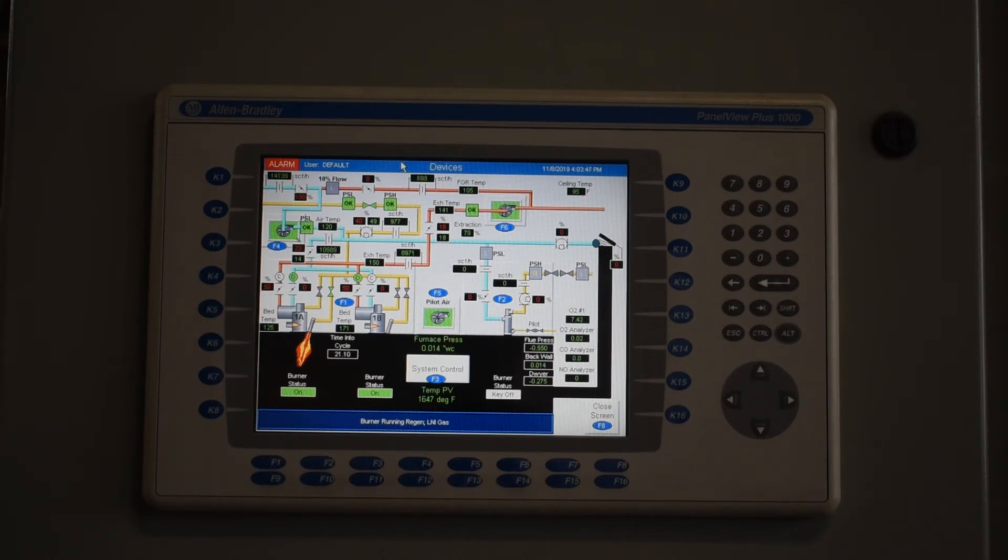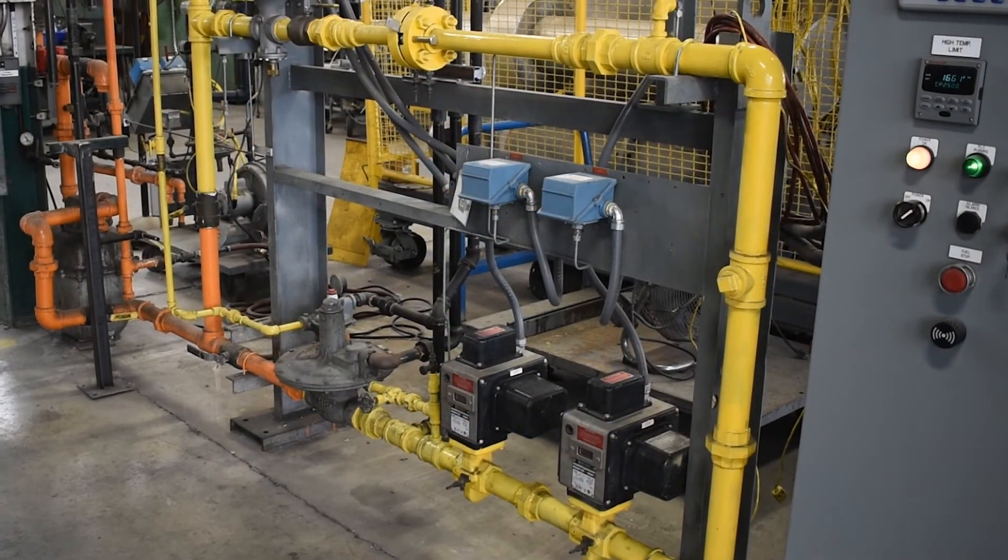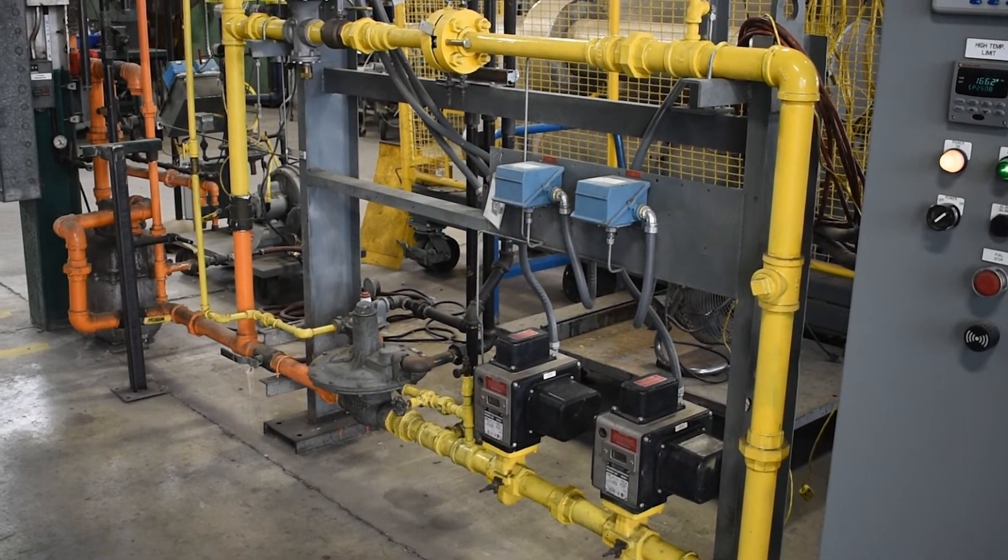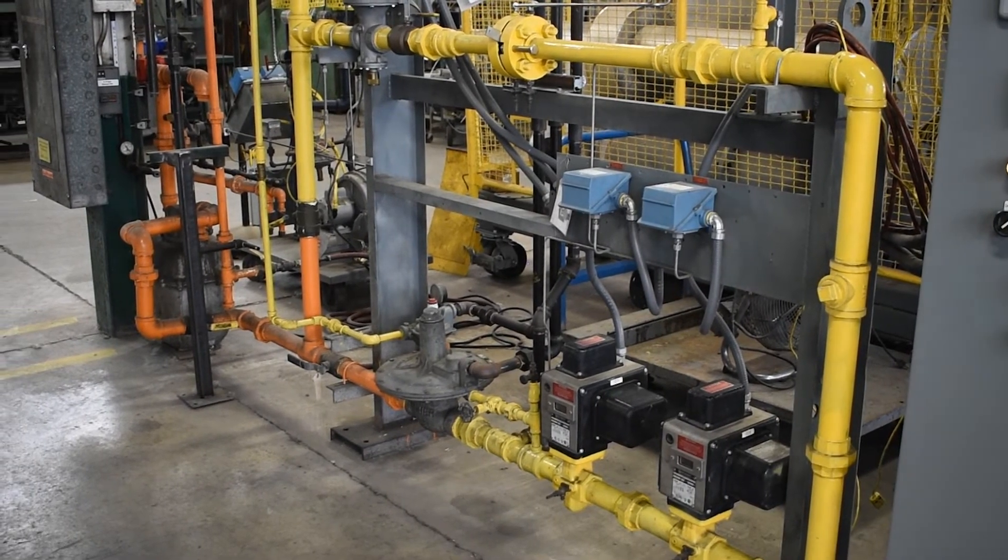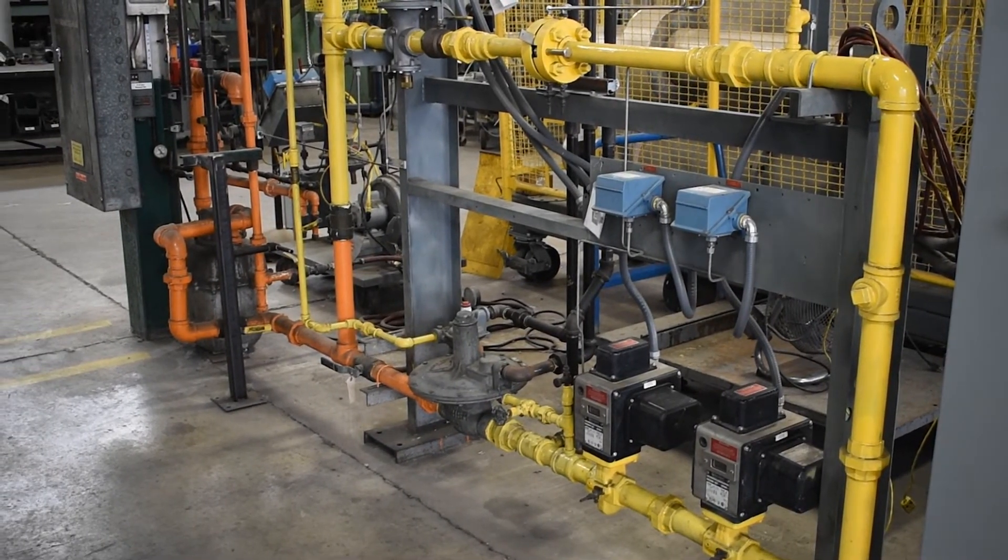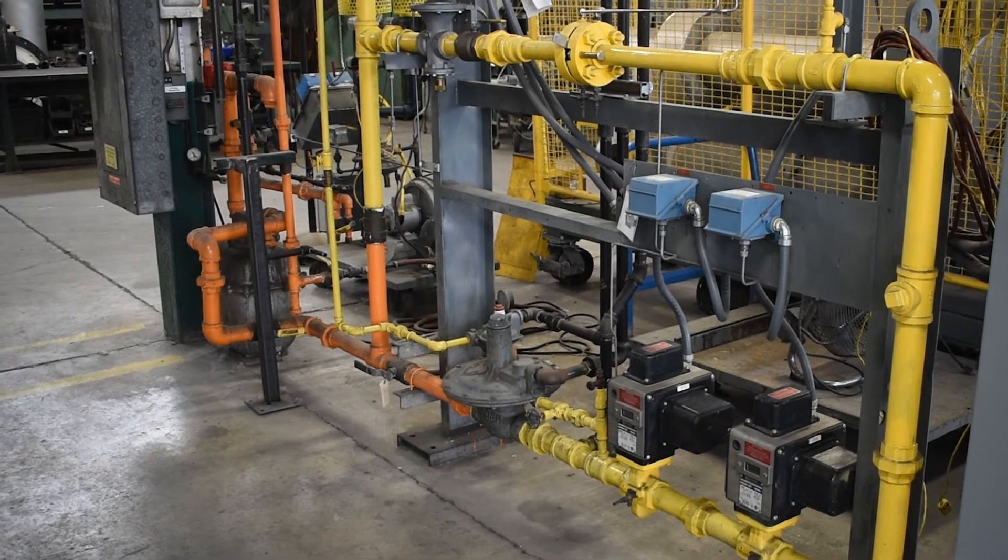To start the system, we begin with the purge. The purge flows combustion air through all air piping to ensure no combustibles are present in the piping or chamber. Four volume changes will be done in accordance with NFPA 86 guidelines. Once the purge is complete, the burners can be started.